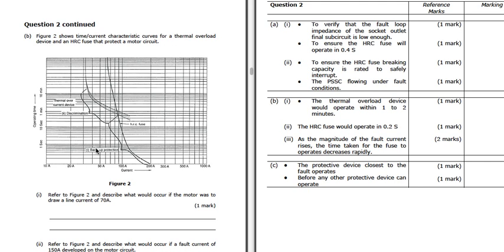We've got a time current graph here, which is that bit shown there, and there's our HRC fuse, and there's our thermal overcurrent protection. We've got to describe what would occur if the motor was to draw a line current of 70 amps. So if we look at the scale on the bottom, it's a logarithmic scale, so it's not linear. So there's our 50, 60, 70. So how long would it take to blow? If we go across, about 1 minute. There's our minute time there. So the thermal overload device would operate within 1 to 2 minutes.